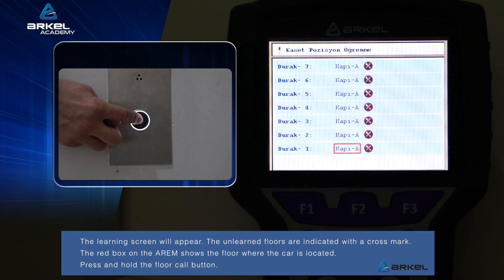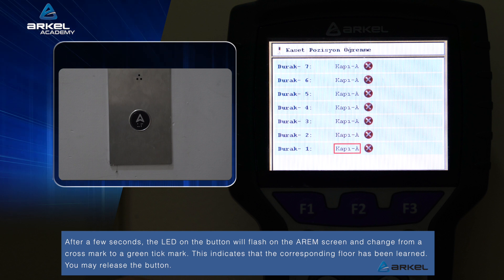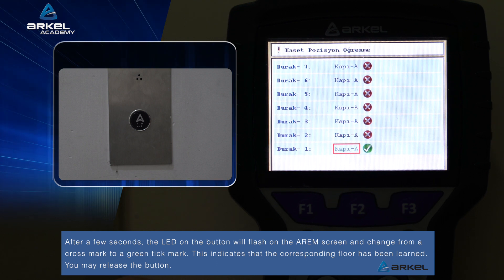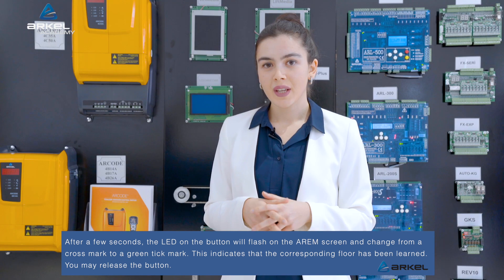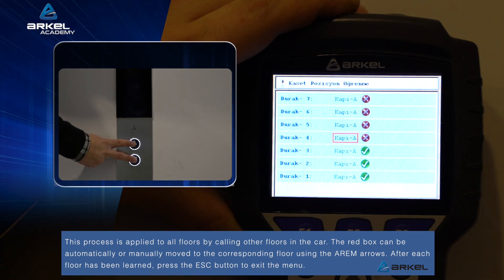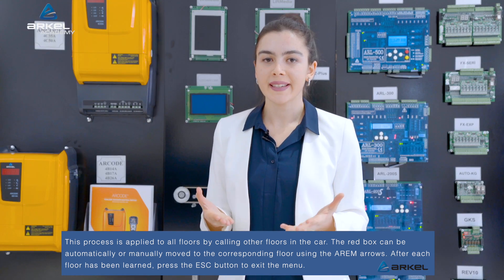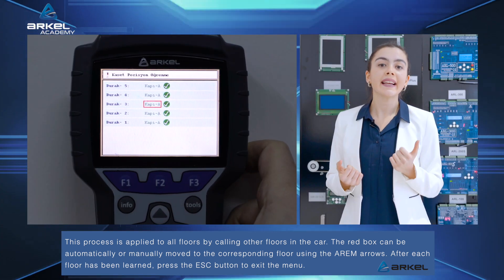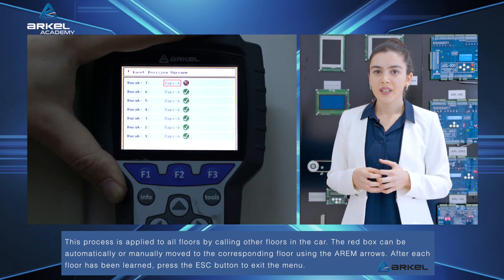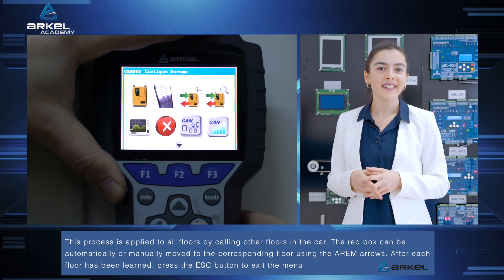Press and hold the floor call button. After a few seconds, the LED on the button will flash on the AREM screen and change from a cross mark to a green tick mark. This indicates that the corresponding floor has been learned. You may release the button. This process is applied to all floors by calling other floors in the car. The red box can be automatically or manually moved to the corresponding floor using the AREM arrows. After each floor has been learned, press the ESC button to exit the menu.